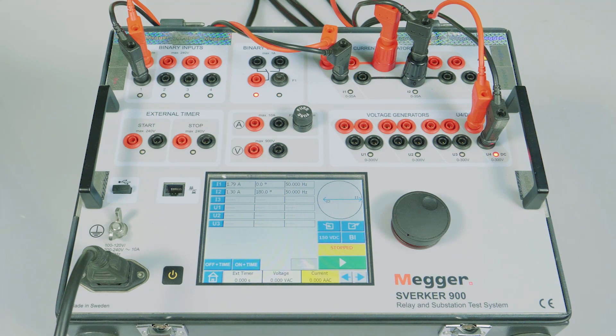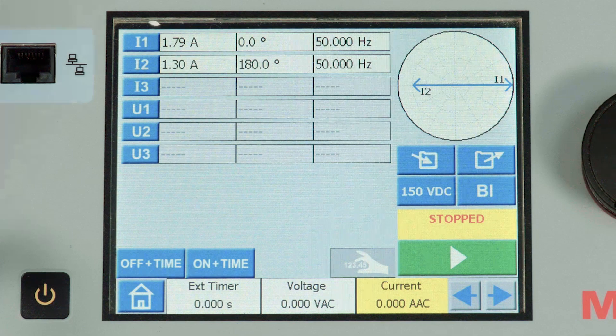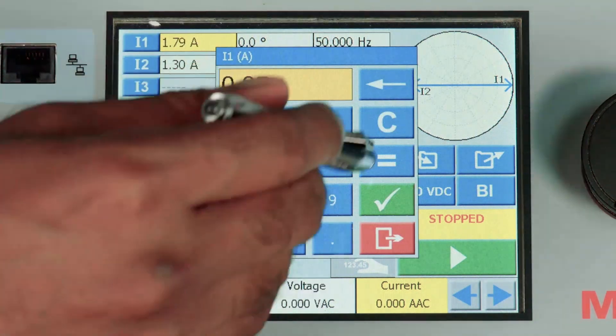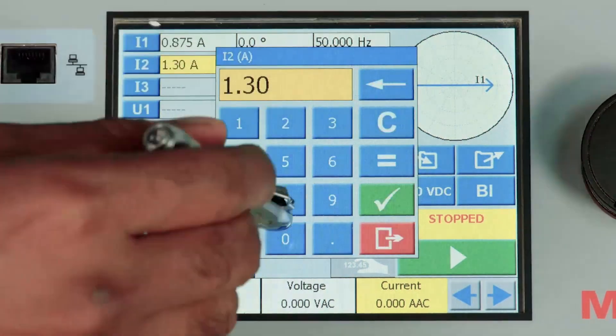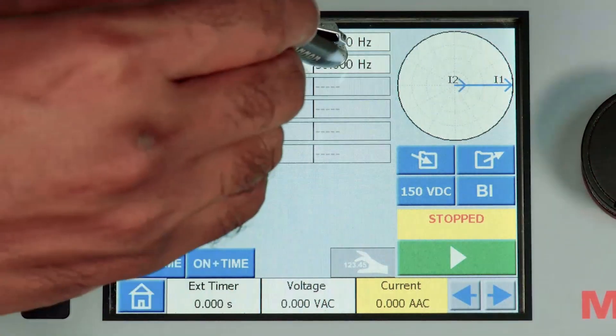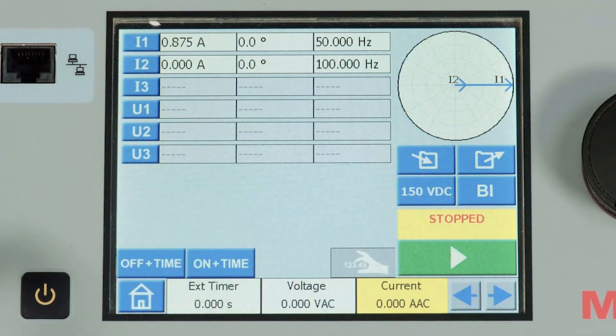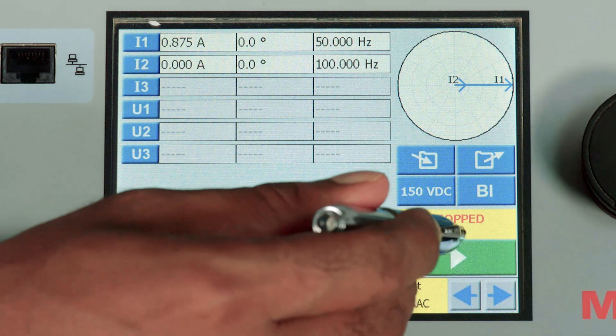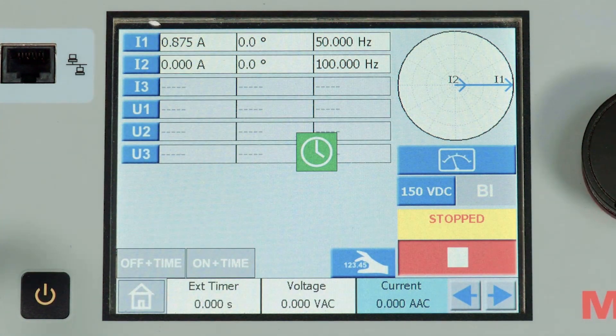Let us test using the operate-to-non-operate method. In this method, we will inject 0.875A angle 0° at 50 Hz in CT1 and 0A angle 0° at 100 Hz in CT2 of the test kit. When the above value is injected, the relay will trip in differential.